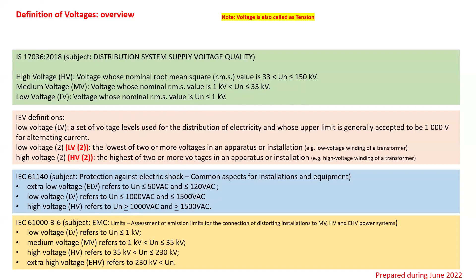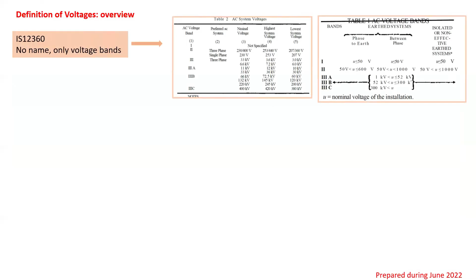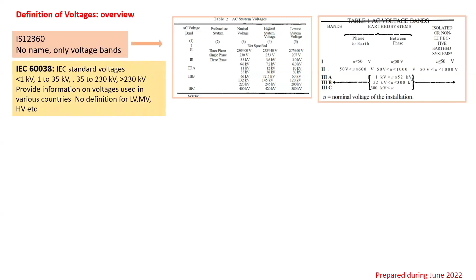In IEC 61140, which is a very important standard because it is the fundamental standard for shock protection, there are only two definitions: low voltage and high voltage. Sometimes another IEC standard may give a different definition, but more or less the IEC definitions remain almost similar, not much change. IS 12360 gives no names, but voltage bands are given. IEC 60038 may be another way of calling it.